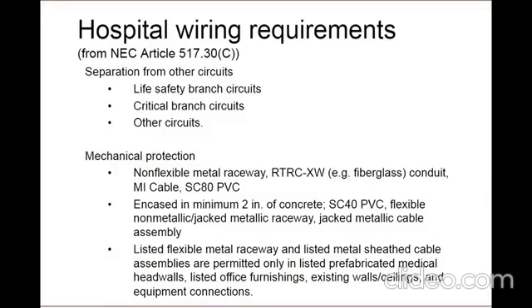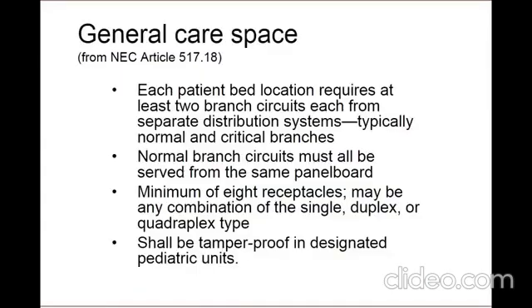The next method is listed flexible metal raceways and listed metal sheath cable assemblies when used in listed prefabricated medical head walls, listed office furniture, in existing walls or ceilings not subject to physical damage, and flexible connection to equipment. The fourth method permits flexible power cords for appliances and other utilization equipment. And lastly, cables for Class 2 and Class 3 systems may be installed with or without conduit.